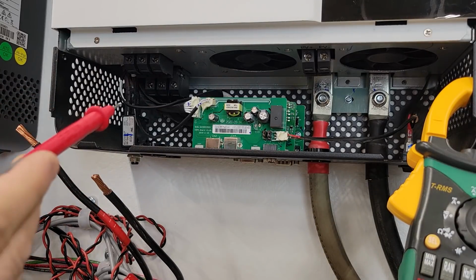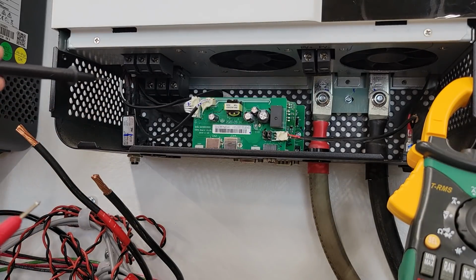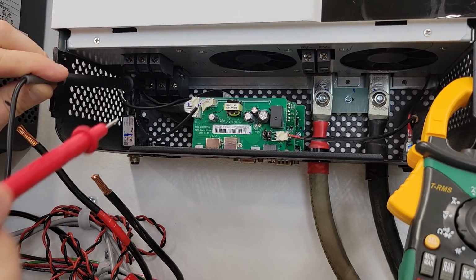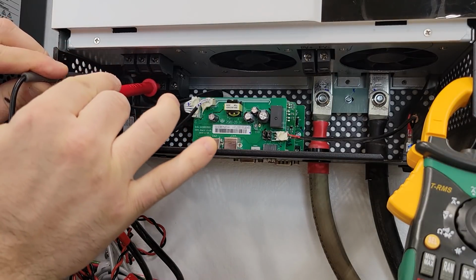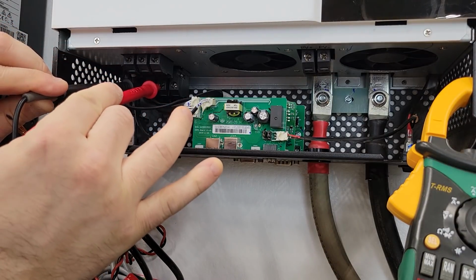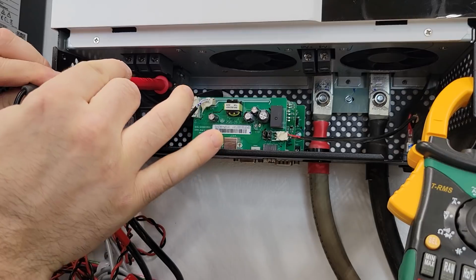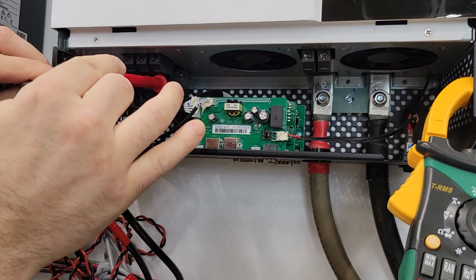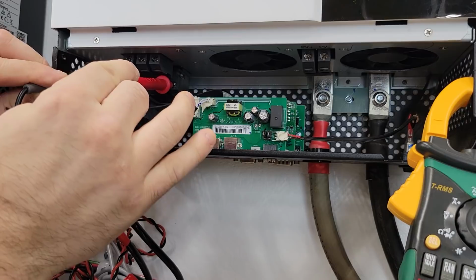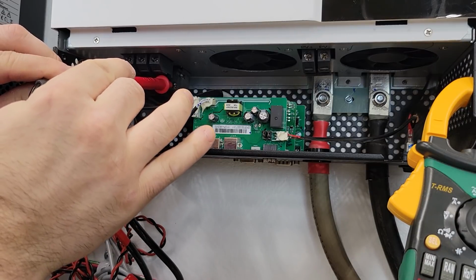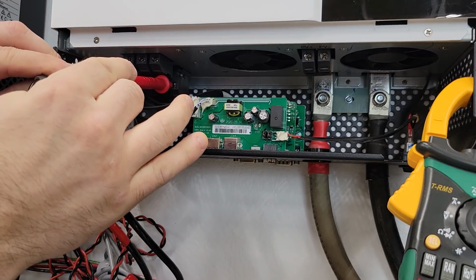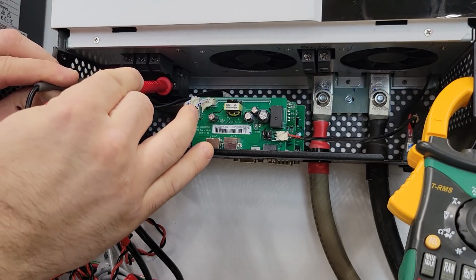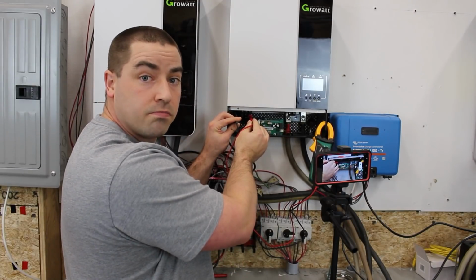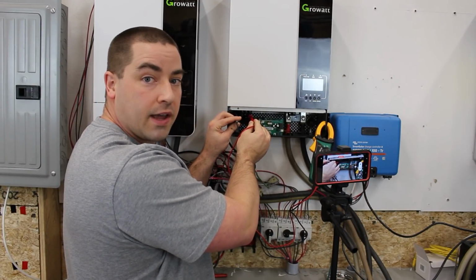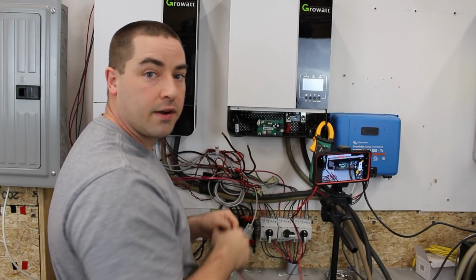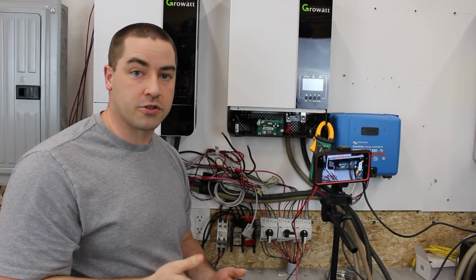So ground is the terminal all the way to the left. Right there. So no ground to line connection and no ground to neutral connection. I don't hear any beeping. And let's just check over here to this one, and no contact between L1 and neutral. All right, so there we go. No continuity between ground and neutral on the Growatt inverter that I purchased from Signature Solar.